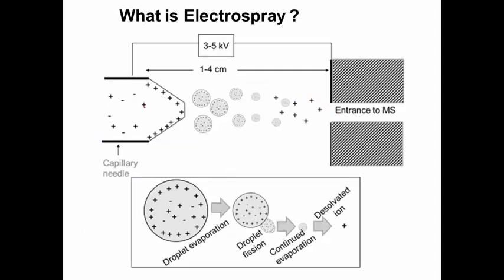If we have our analyte, say M, and then it's protonated, which gives it that positive charge, our needle is going to have a very high positive potential applied to it. If our ions are positive, they're going to be pushed to the other end because they don't like this positive potential. The mass spectrometer itself is going to be held at ground.